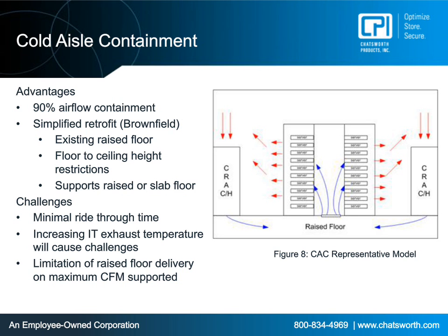This, though, the lid style, the cap style, one of the advantages of that is it is very easy in the field to retrofit. Most of the time when you're just putting a lid right over the top of the cabinet, you don't encroach on anything: ladder rack, power busway, fiber runs, anything like that. So it is one of the more simplified retrofits you can do out there in a brownfield situation. You can do it on slab floor, raised floor. I've done one where I've lidded a cabinet aisle, and then we've piped the cold air down from above into the aisle. It does not have to be on a raised floor. My graphic does show a raised floor, but it does not have to be there.